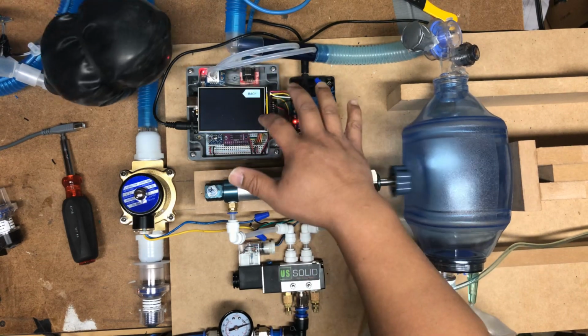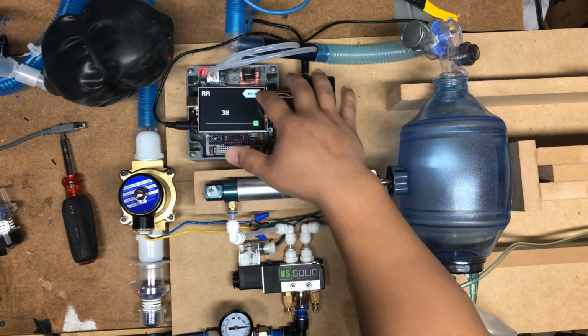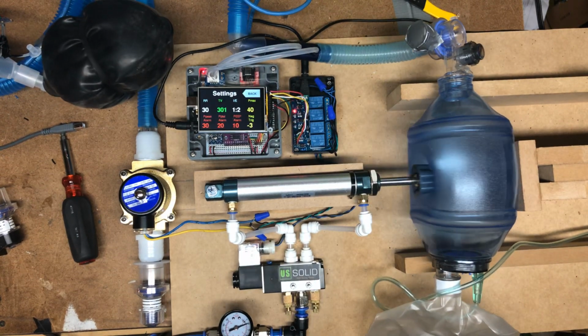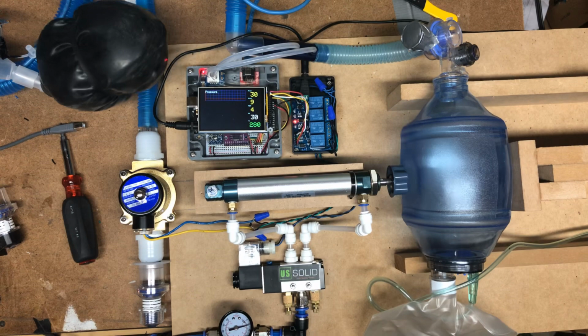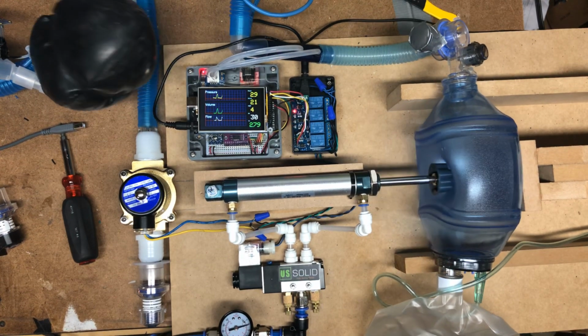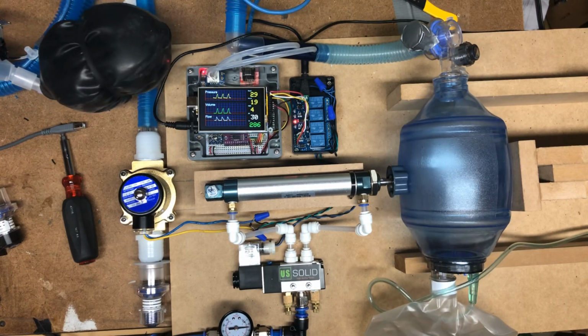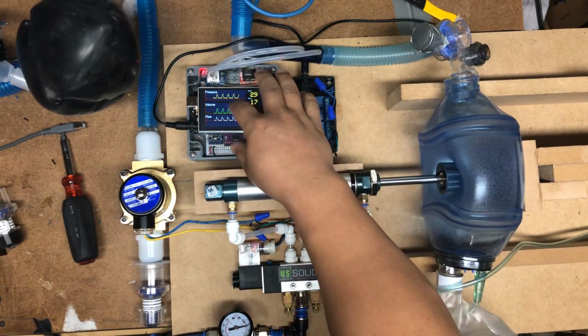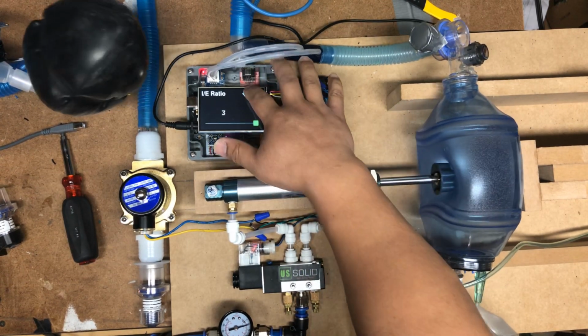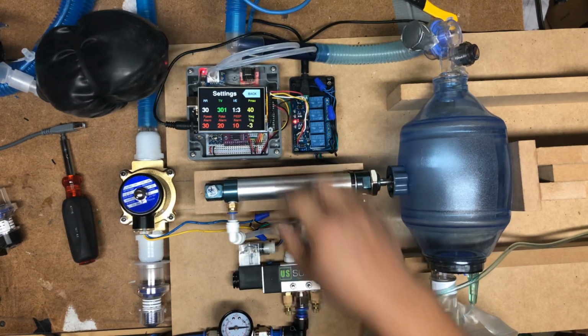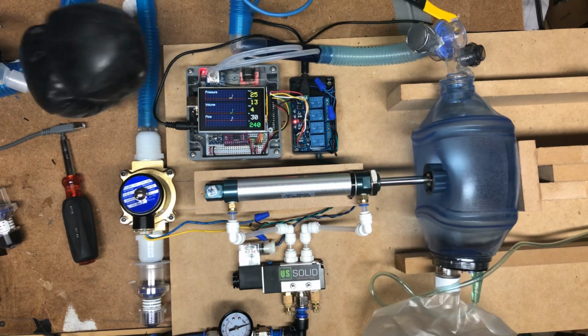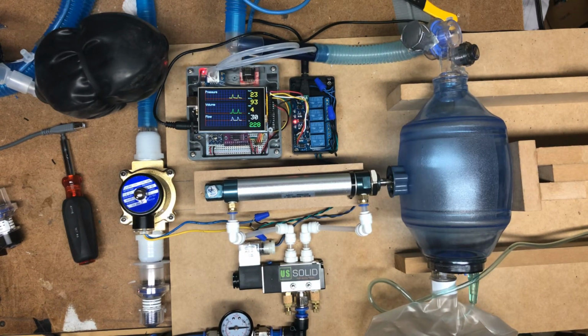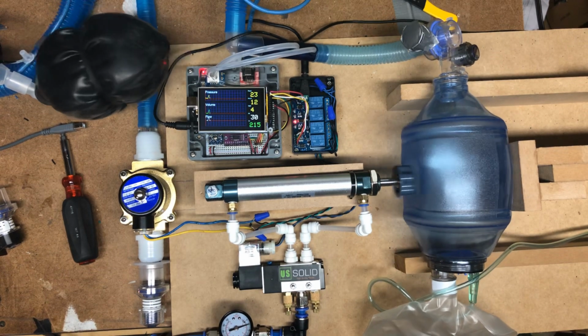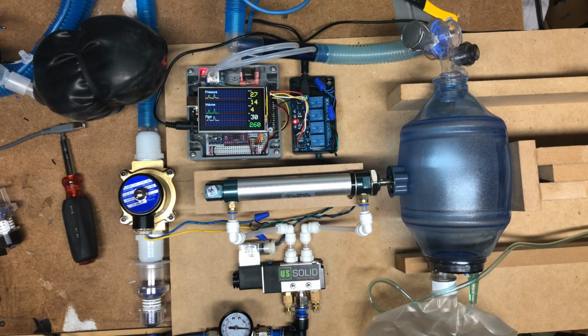Change the respiratory rate up to, say, 30. Change the I:E ratio up to, say, 3. Try that. It's having trouble achieving the tidal volume because the inspiratory phase is pretty short. We can up the pressure to give it some more power.